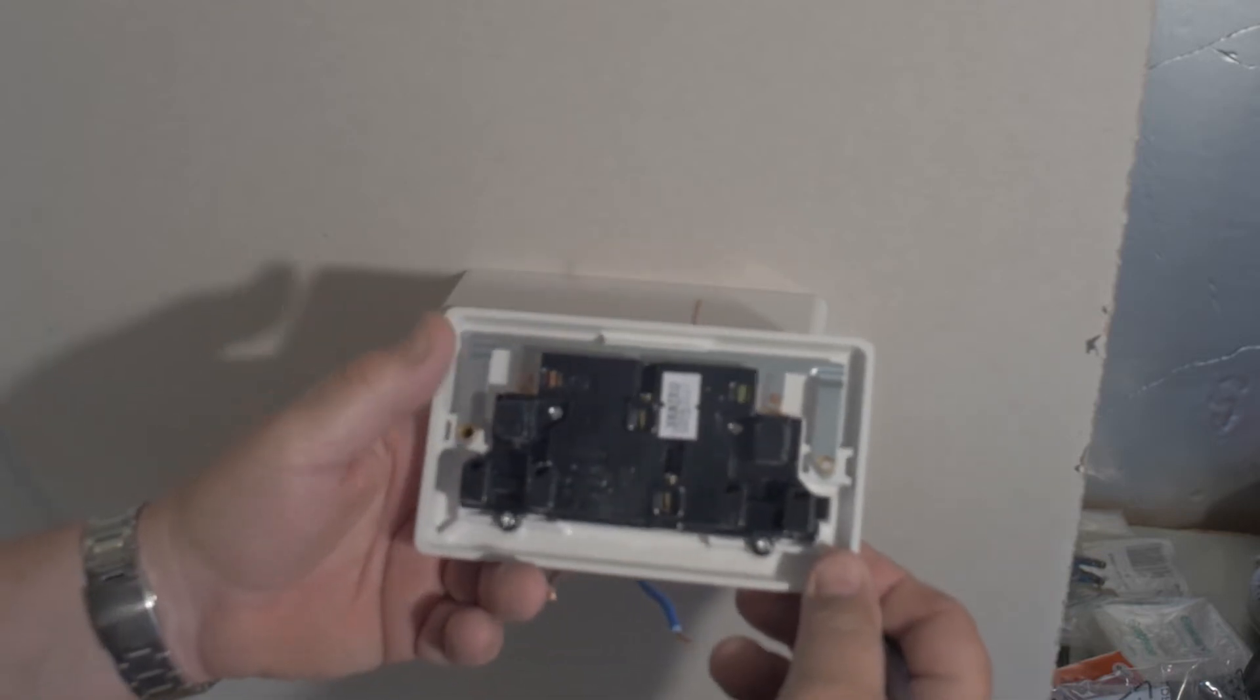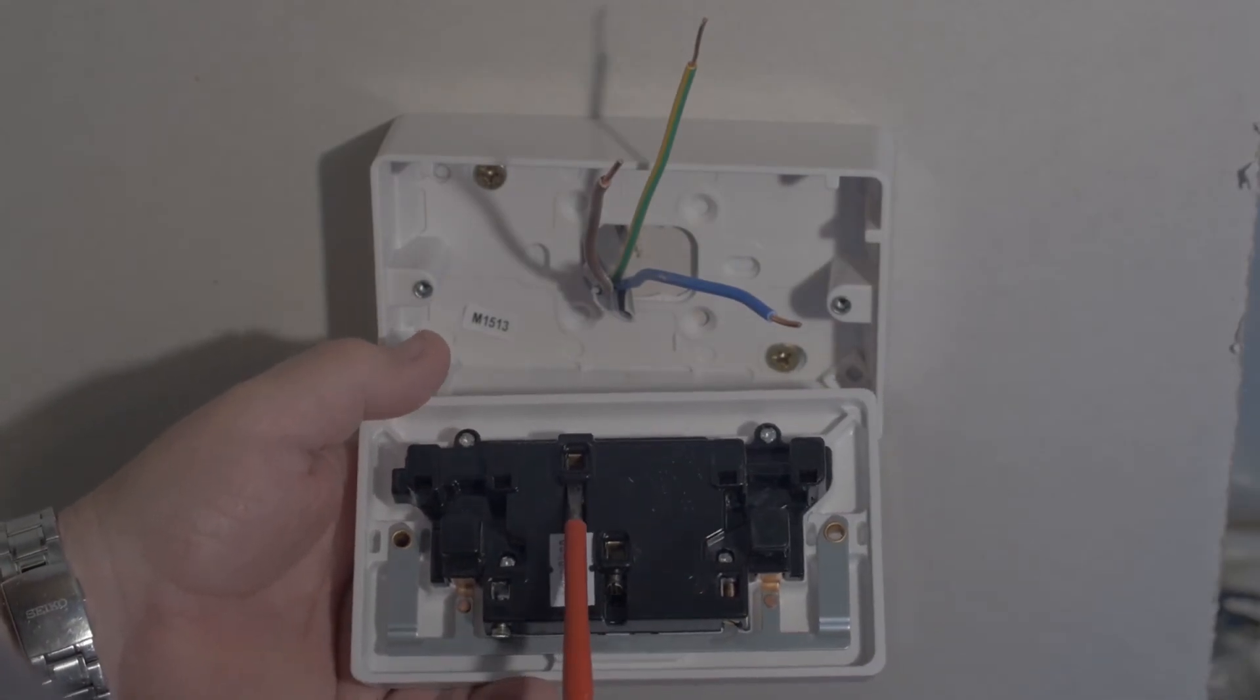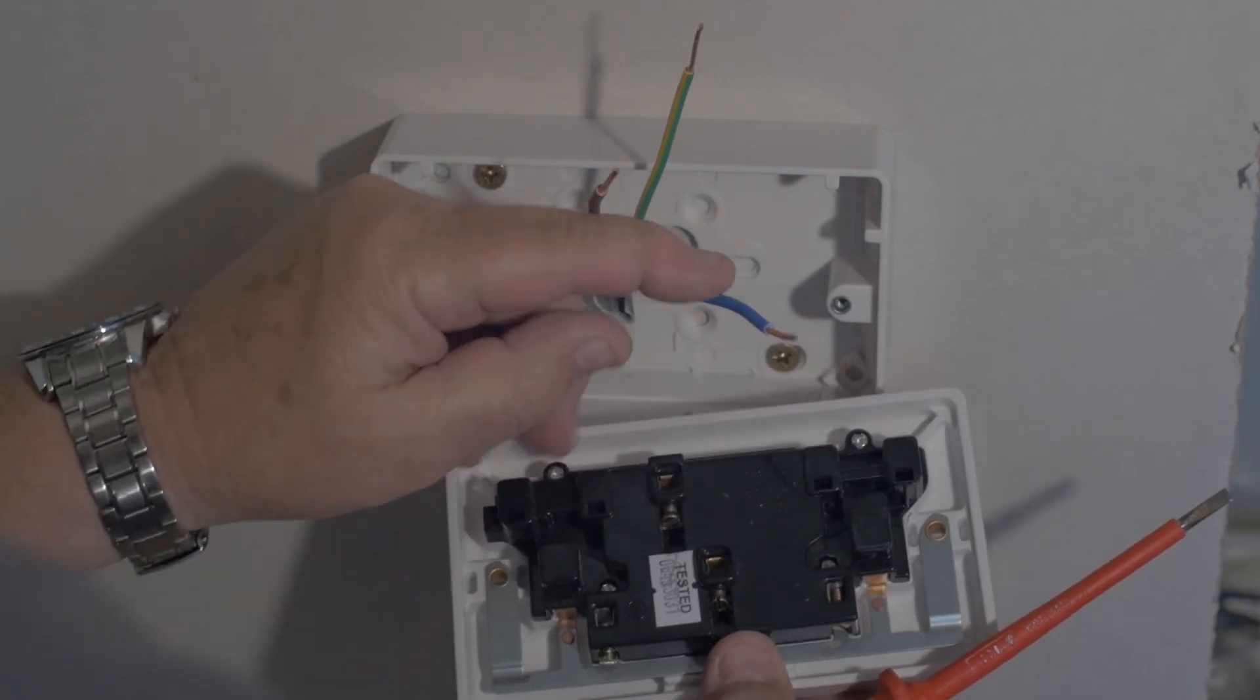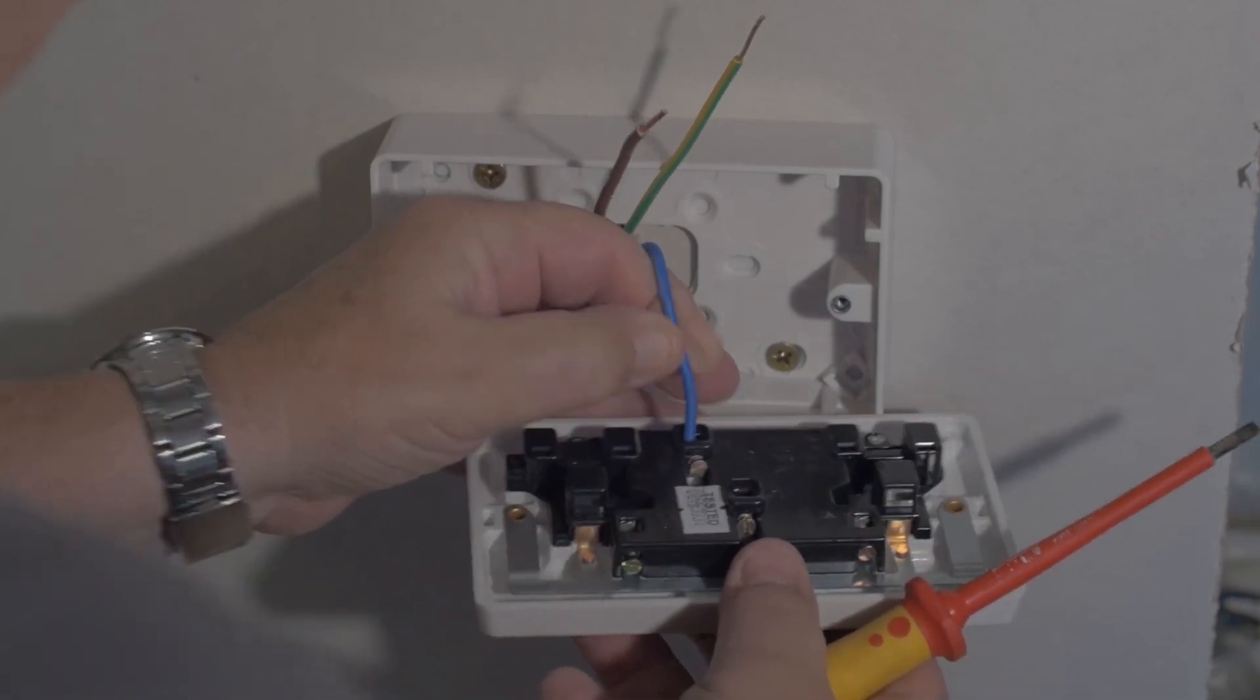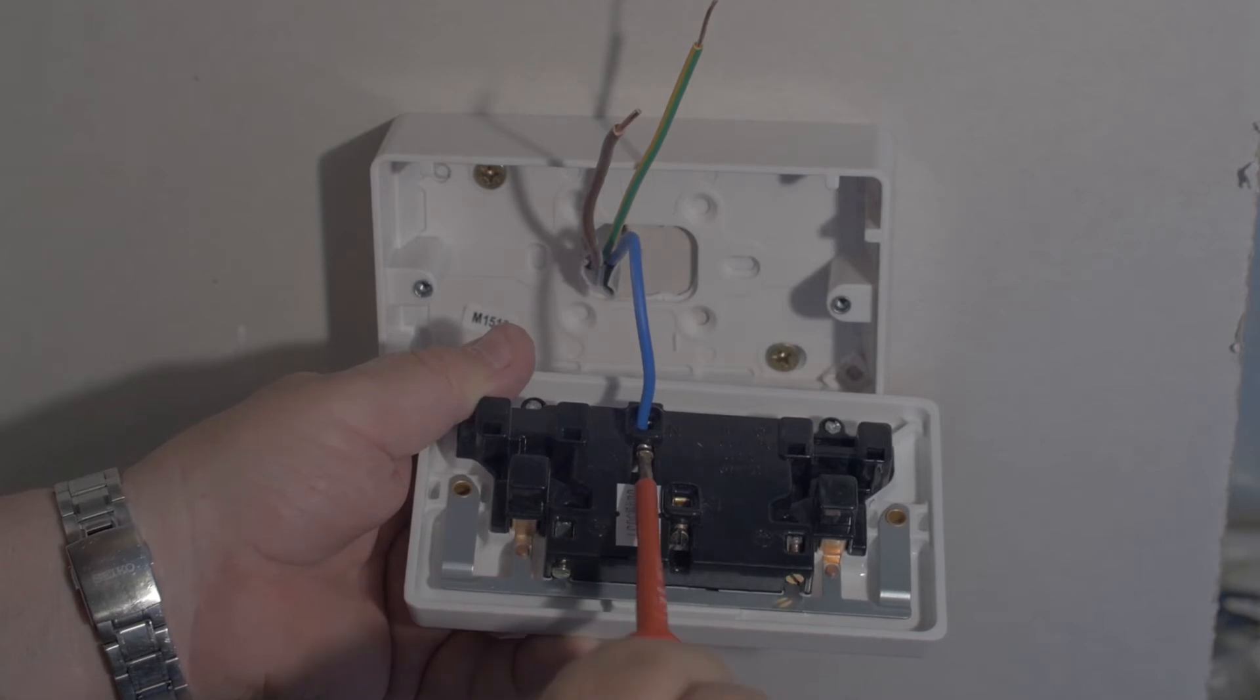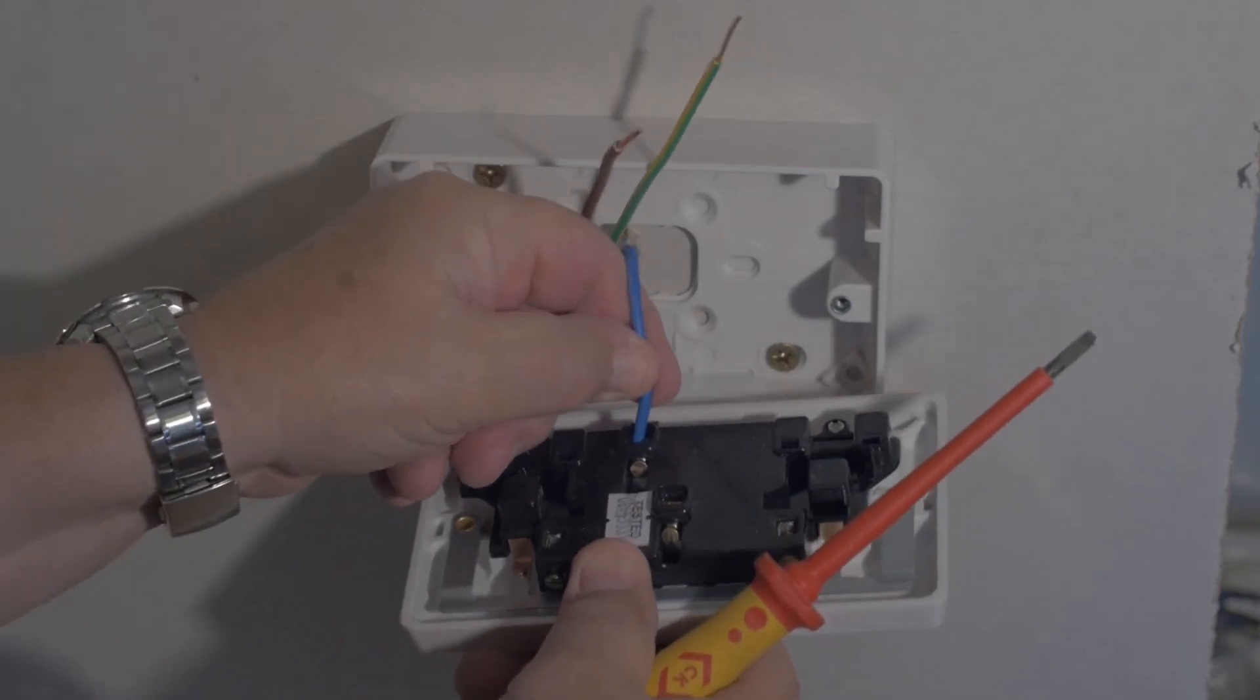Now we're going to install the wires. So just loosen the screws - neutral, live, and the earth - so that your cable will allow to go into the unit itself. So now we take the first cable, which will be the blue, which is the neutral, put that inside to the socket and tighten down. Tighten down until it's snug and then give it one half turn, and that will secure it so that we're nice and tight with the cable.